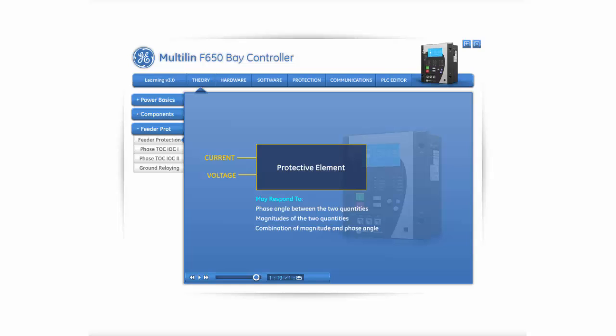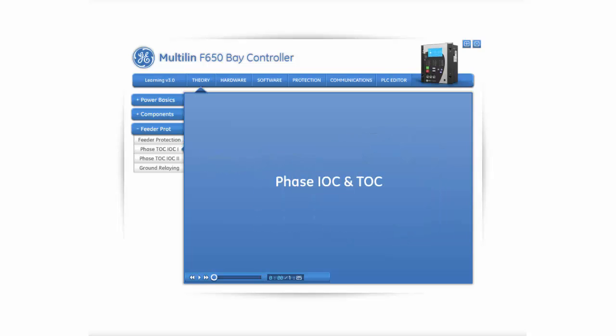In protective relaying, it is common to use an operating characteristic to show the relationship between the quantities that will cause the relay to operate. As stated earlier, if only one measured quantity is used, the protective element will respond to the measured quantity over time. The operating characteristic will take the form of a graph, with the measured power system quantity plotted on the x-axis against time on the y-axis. The graph, or operating characteristic curve, clearly demonstrates the boundaries between three regions. The first is the non-operate region, and as the name implies, the element will not operate when the intersection of the two measured quantities falls within this area. The second is the curve, which represents the point at which the element picks up. The third region is the operate region. The element will operate when the intersection of the two measured quantities falls within this area.